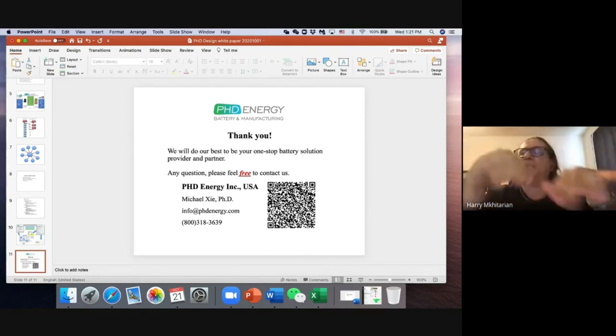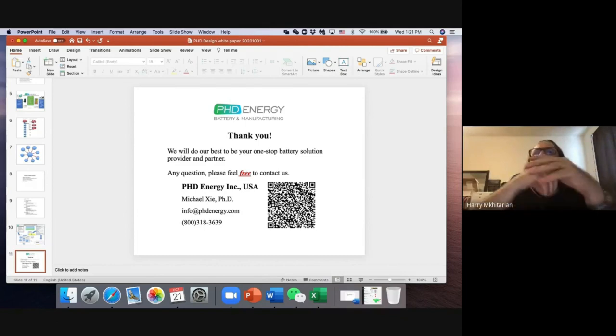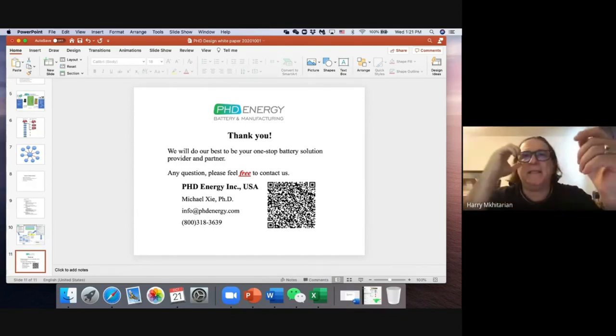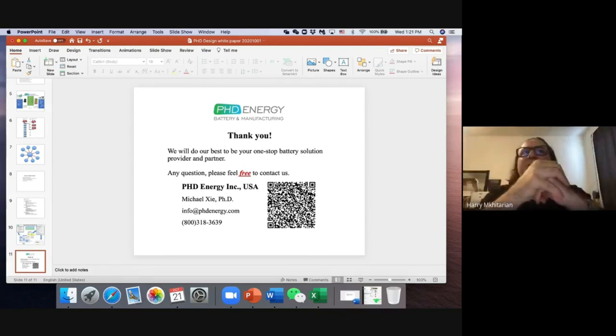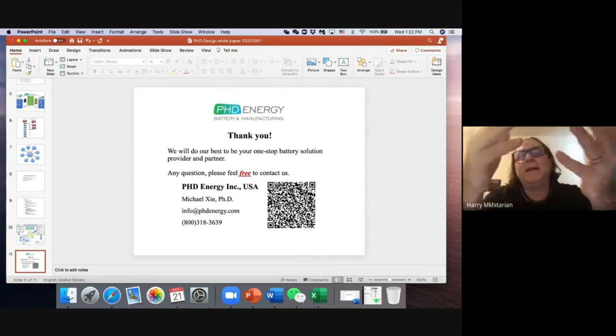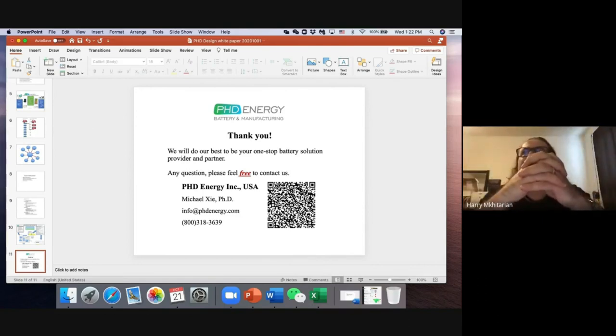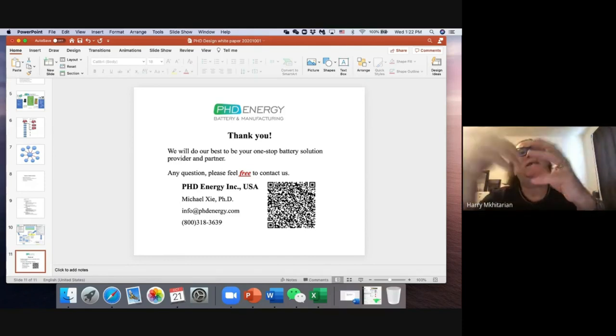You could just go into sleep mode. Even if we put in a protection module, the BMS itself has some drain on the battery, it does pull some current, and then you've got your own circuitry that will drain as well. So if that drain is low enough, you might think, okay, I can survive this. We can ship pre-charged from the factory, but not 100%, because the UN38 requirement is about 30 to 40%.